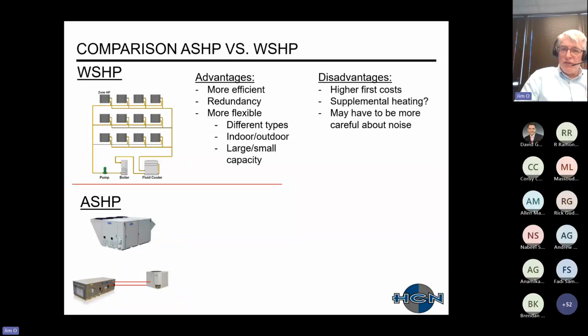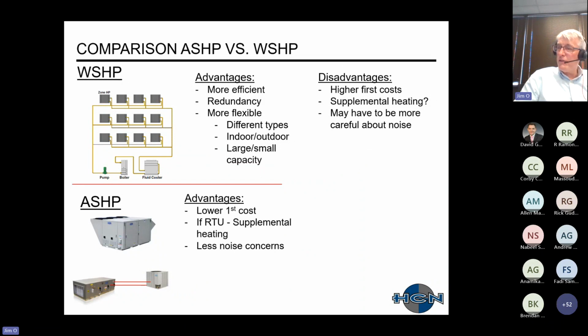The disadvantages: traditionally it does have a higher first cost. Supplemental heating can be problematic, either with your boiler, or you have to add it at your system and stuff like that. And then just realize that if you have water source heat pumps that are in spaces, you have to be cognizant that the compressor does run. The compressor could potentially make objectionable noise.